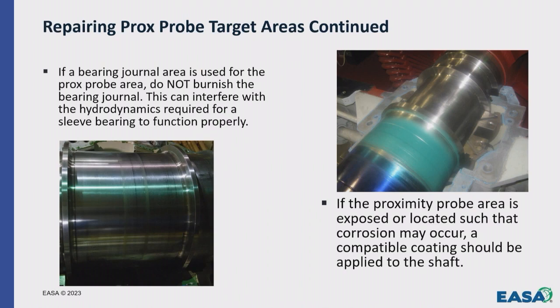So occasionally when people, especially when they add prox probes, they'll put them targeting a bearing journal. They'll actually go through the top of the bearing, which is fine. Once again, it's not quite as fine a finish as we see with a burnished area, but it does work and it works well. So we see it pretty often when they go there, or a lot of times the other popular place is a seal area if it did not come with a burnished area.